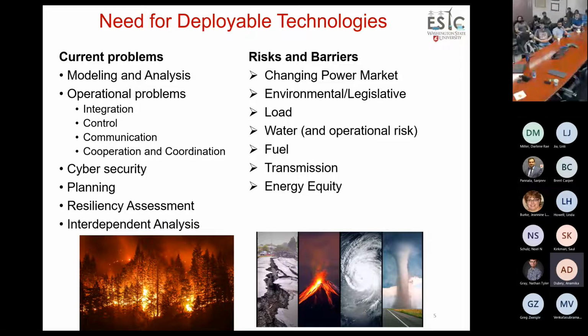Then there's the communication side - the infrastructure, because there are a lot of protocols. Every time you come up with different protocols, you change them to make it more secure. Previously, most of the time they used Modbus, generally for the DERs. Now we're changing to DNP3 on the substation side, and Goose protocols, and now we have CAN bus on the battery side. These communications keep changing and upgrading. Taking PMUs, wide area measurement side, they had the 1.0 framework, now 2.4 has already come out. So different frameworks keep coming up with different ways to upgrade.